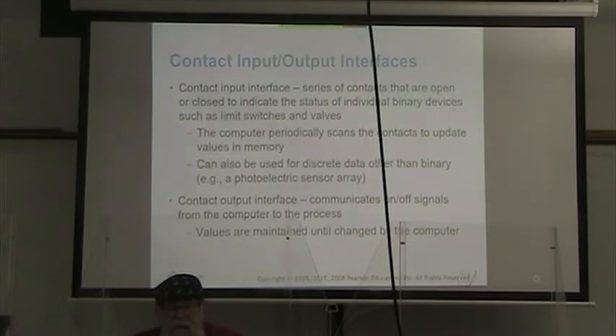These contact input and output interfaces, the contact input interface is contacts that are open or closed to indicate the status of individual binary devices, such as limit switches and valves. The computer scans the contacts and updates the values in the memory periodically. This could also be used for discrete data that is not binary, such as photoelectric sensors. A contact output interface communicates on-off signals from the computer to the process. And those values are maintained until they are changed by the computer.